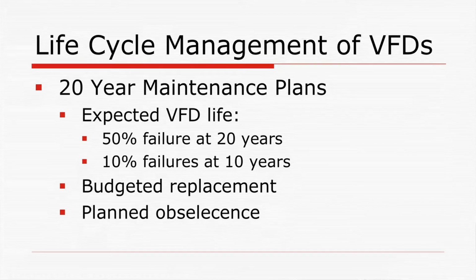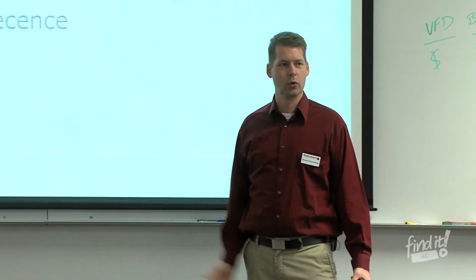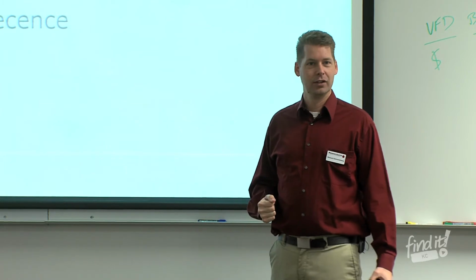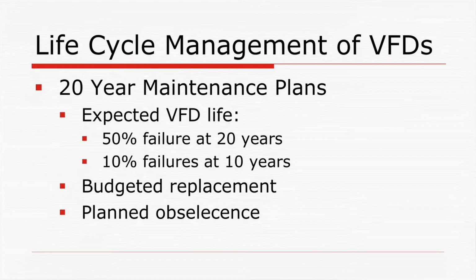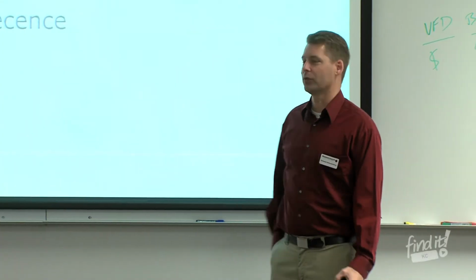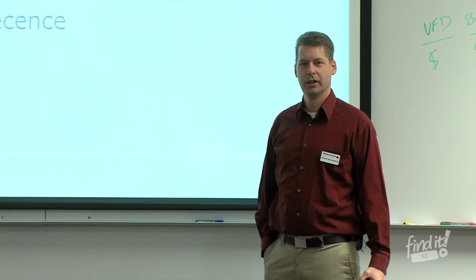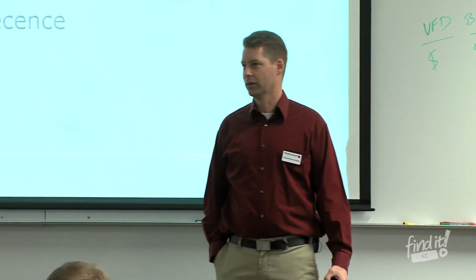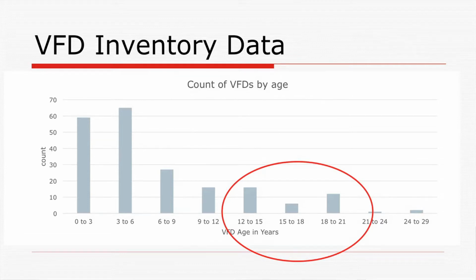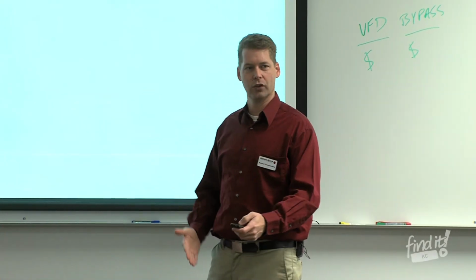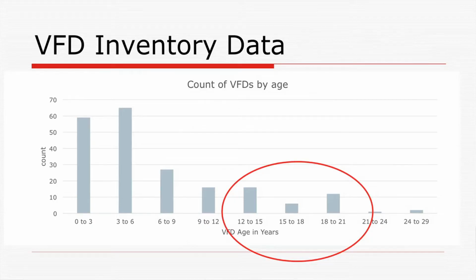So with the 20-year maintenance plan that they wanted, we came up with, through multiple conversations, and I knew most of this from working at ABB, how long does a VFD last? It's an electronic piece of equipment that we're expecting is going to have about a 15-year usable life. And when you break it down, we're expecting actually 50% of the VFDs to fail by their 20th birthday, and 10% of the VFDs to fail at their 10th birthday. So that's just a rough generic idea of the failure rates of VFDs. And with that and knowing the age of your equipment, you could then start budgeting for replacement. You could then get it into next year's budget. Say, I've got 10 VFDs that are somewhere between 12 years and 15 years old. We're going to have a certain number of those that are going to have to be replaced.